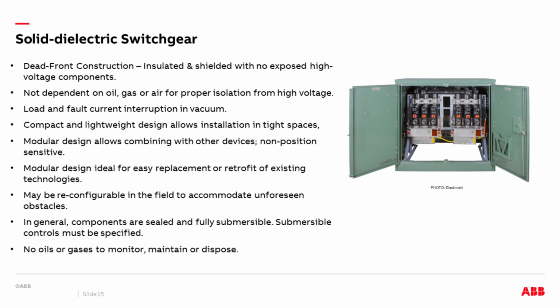So all the load and fault current interruption is in vacuum. There's no oil or gas or air to manage or worry about. Compact, lightweight, fits in tight spaces. One of the key features about solid dielectric gear is it's modular, so you can take components out, move them around. It gives us flexibility of how we create gear to fit existing installations for replacement, which is the key point of this presentation. So this modularity and reconfigurable features helps us to accommodate customers who have specific cable positions, specific bushing heights, for example, and size restrictions on the pads.